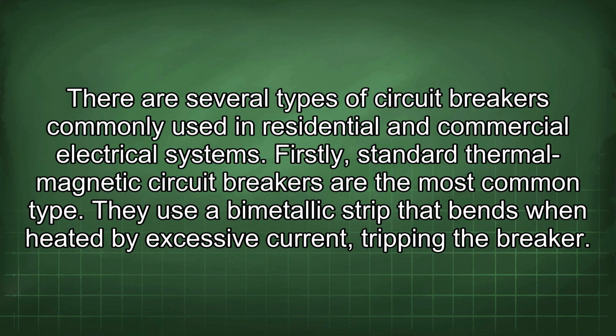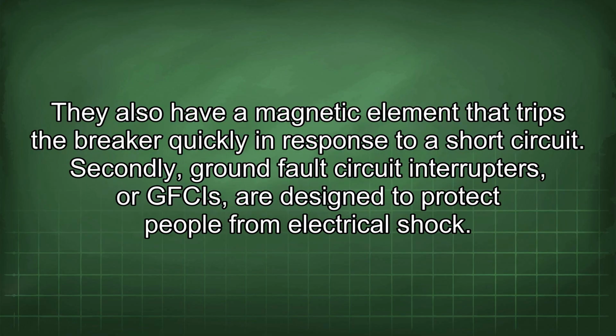Firstly, standard thermal magnetic circuit breakers are the most common type. They use a bimetallic strip that bends when heated by excessive current, tripping the breaker. They also have a magnetic element that trips the breaker quickly in response to a short circuit.